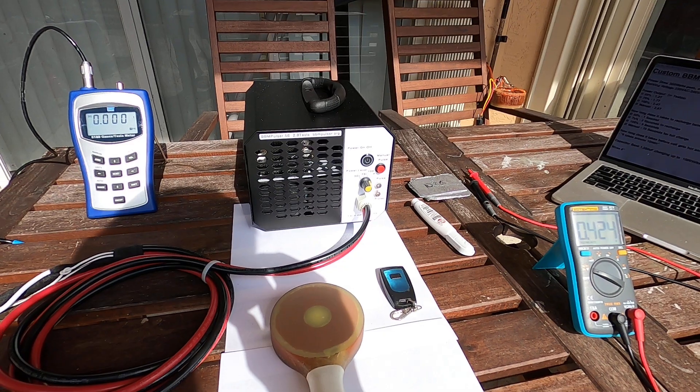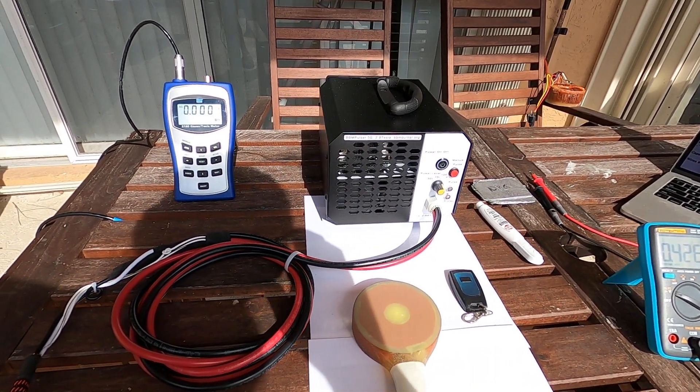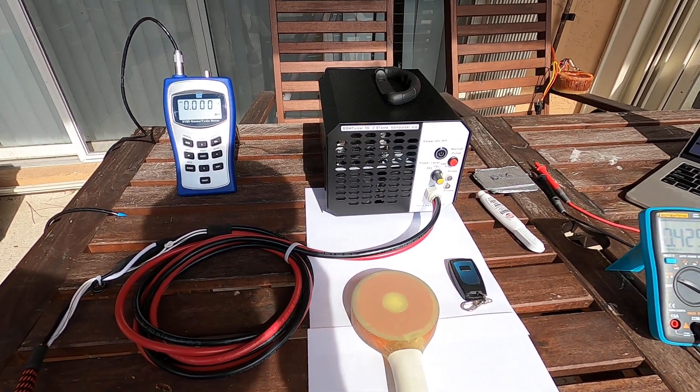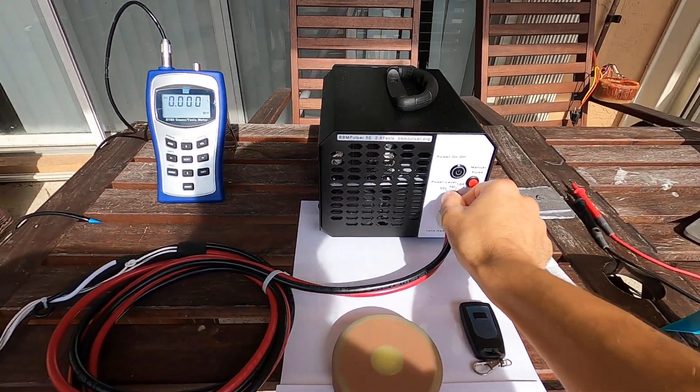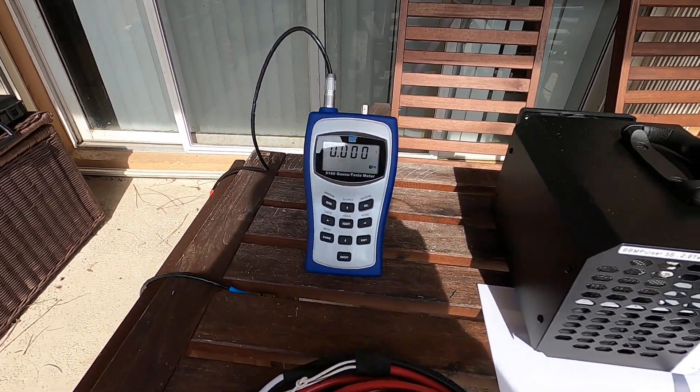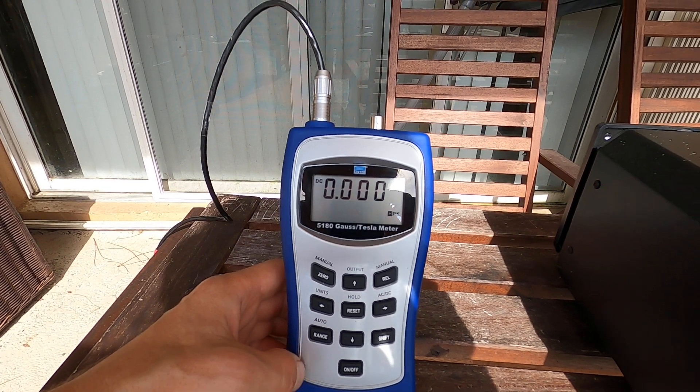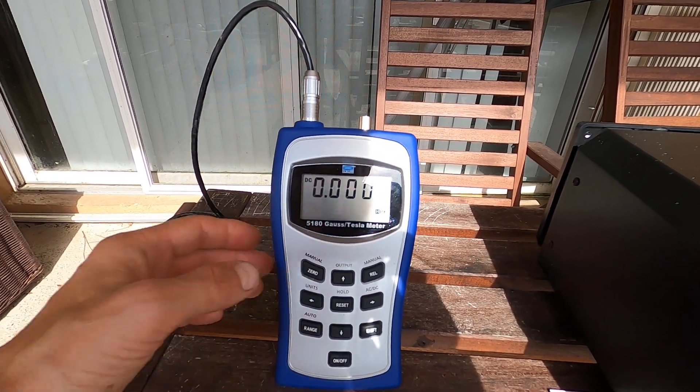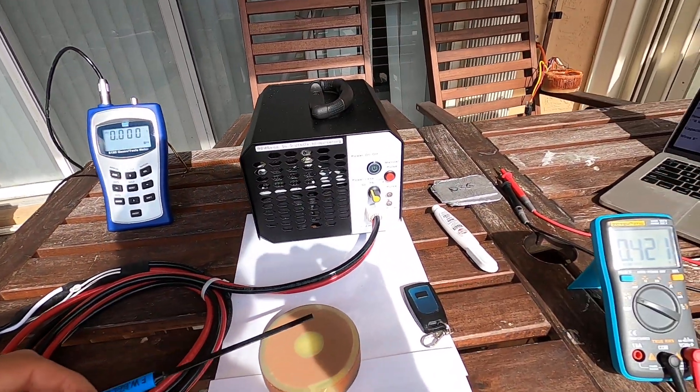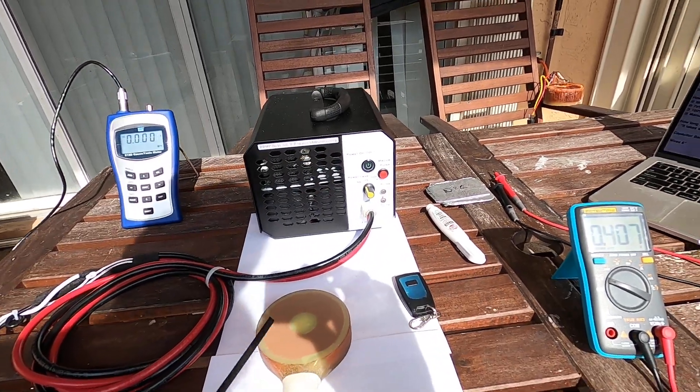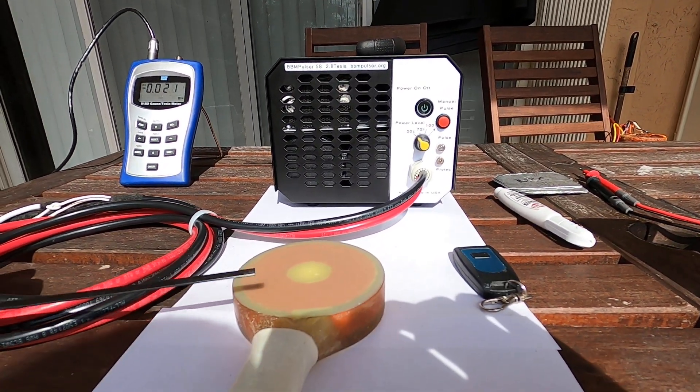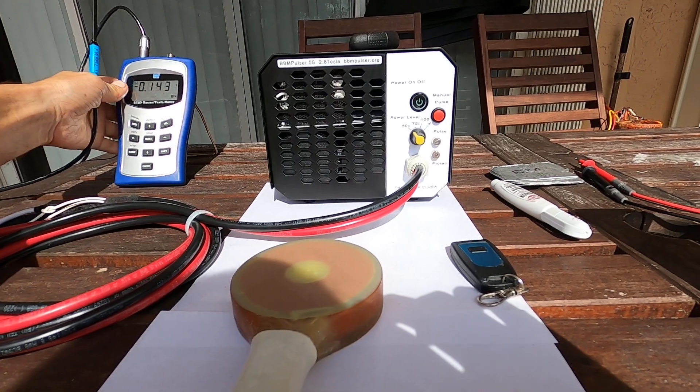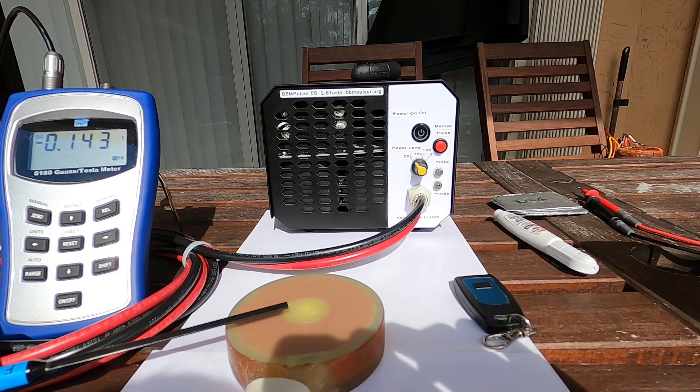So let's give it some power tests and I'm gonna show you how this unit performs and what it's capable of. Let's start with power test at 50 percent. And I'll have my Tesla meter here. It's already set to pick the highest value. I have my probe here. So let's go ahead and start the unit, take some measurements at 50 percent. I'm gonna bring the Tesla meter closer so we can see measurements.